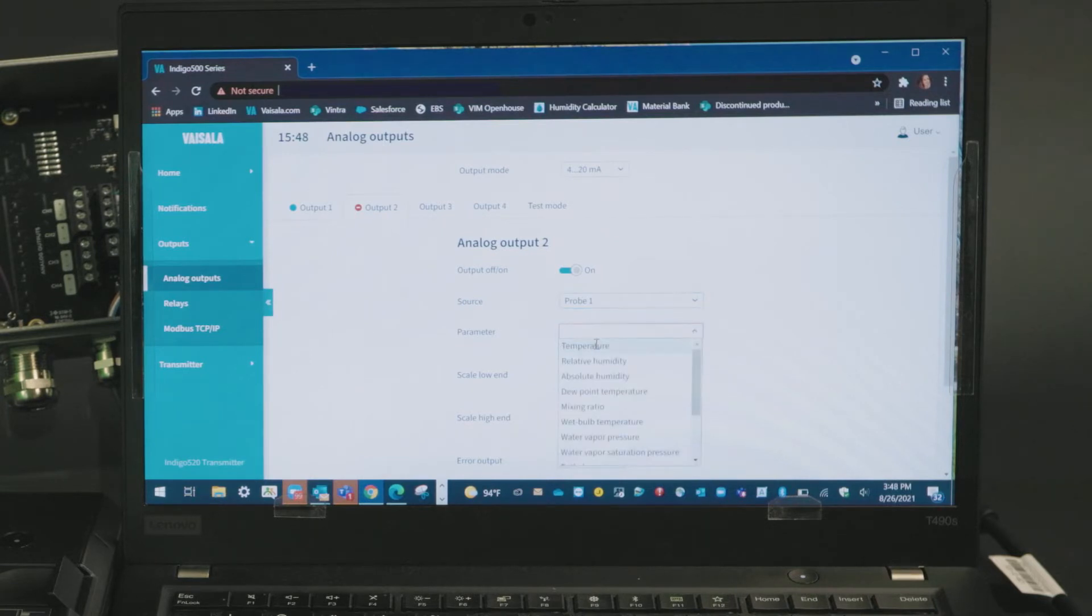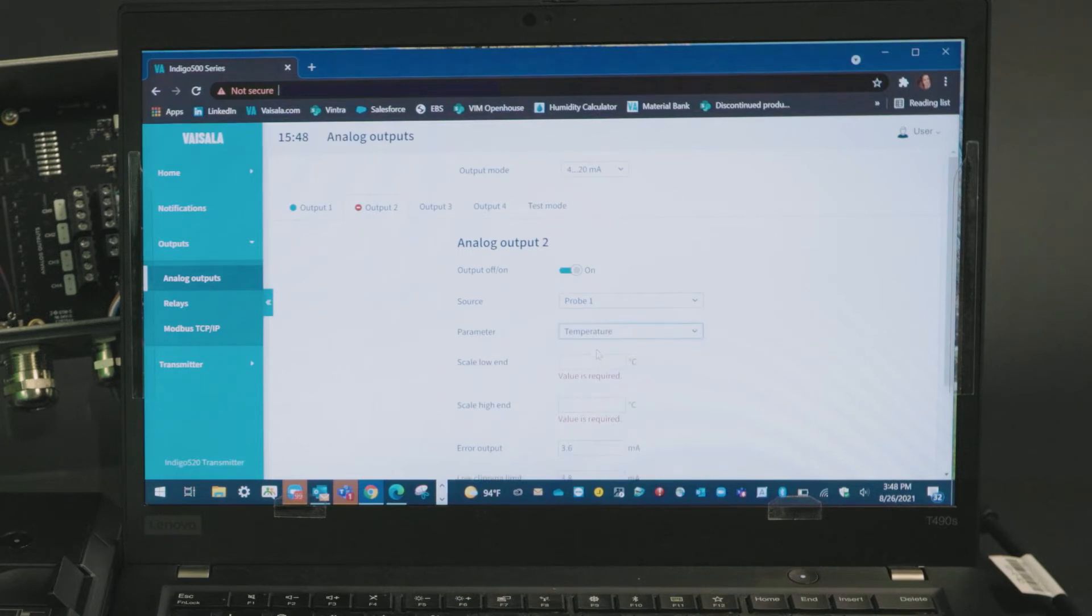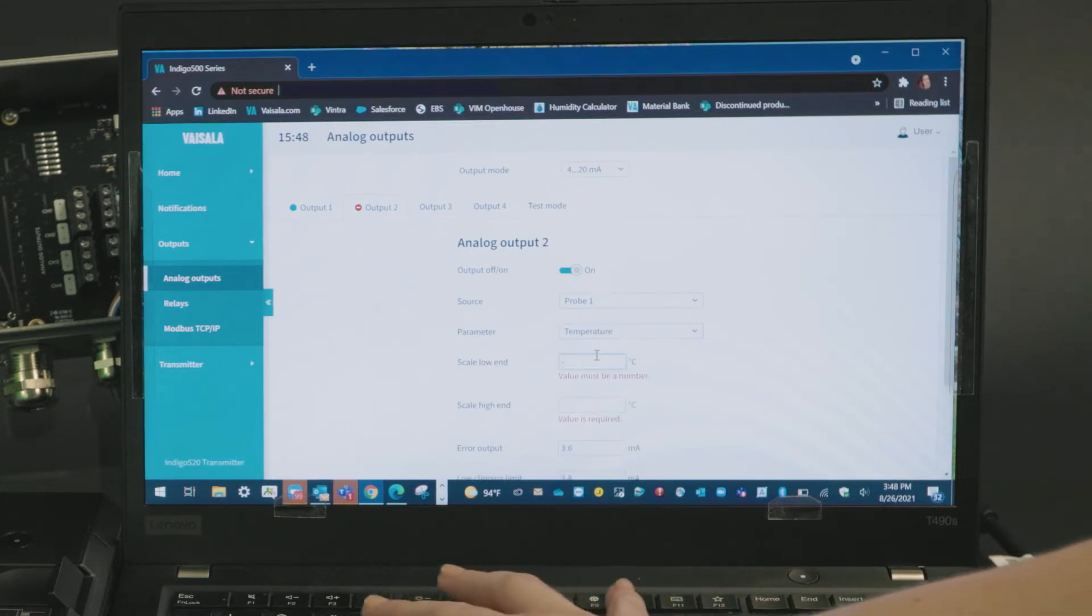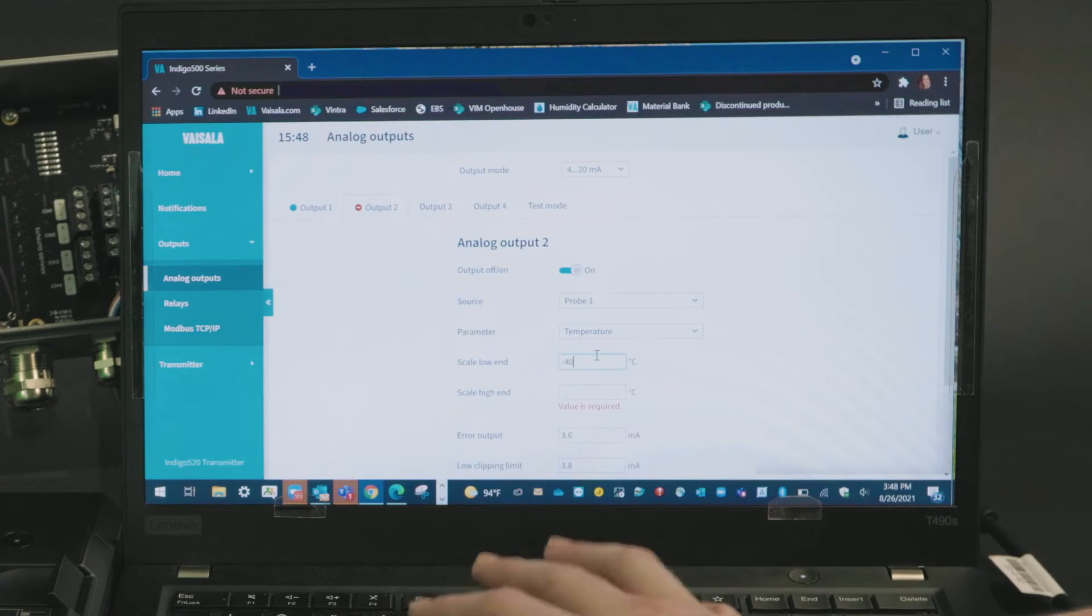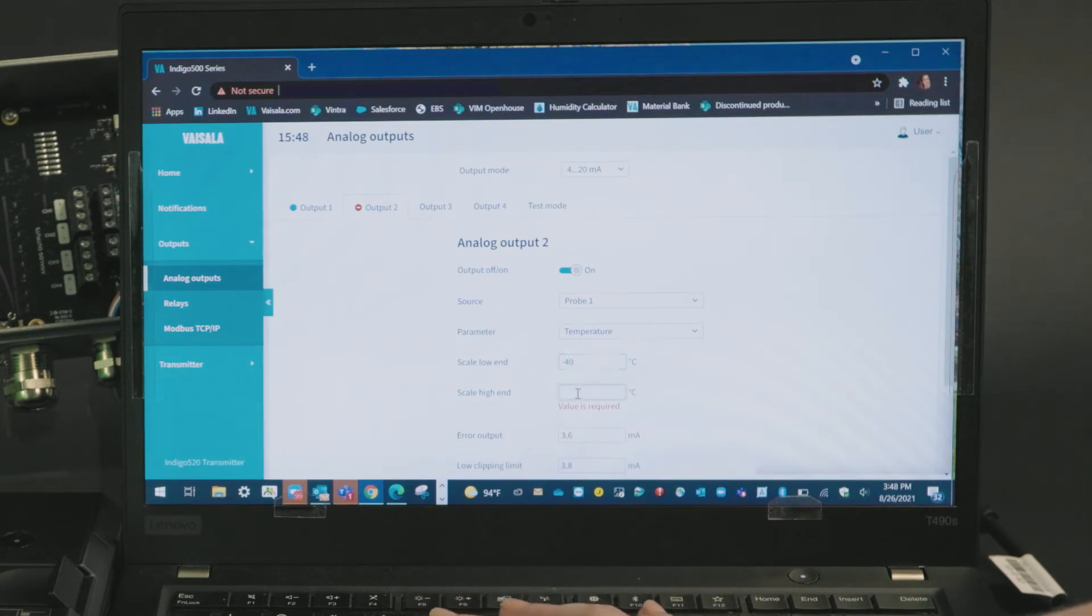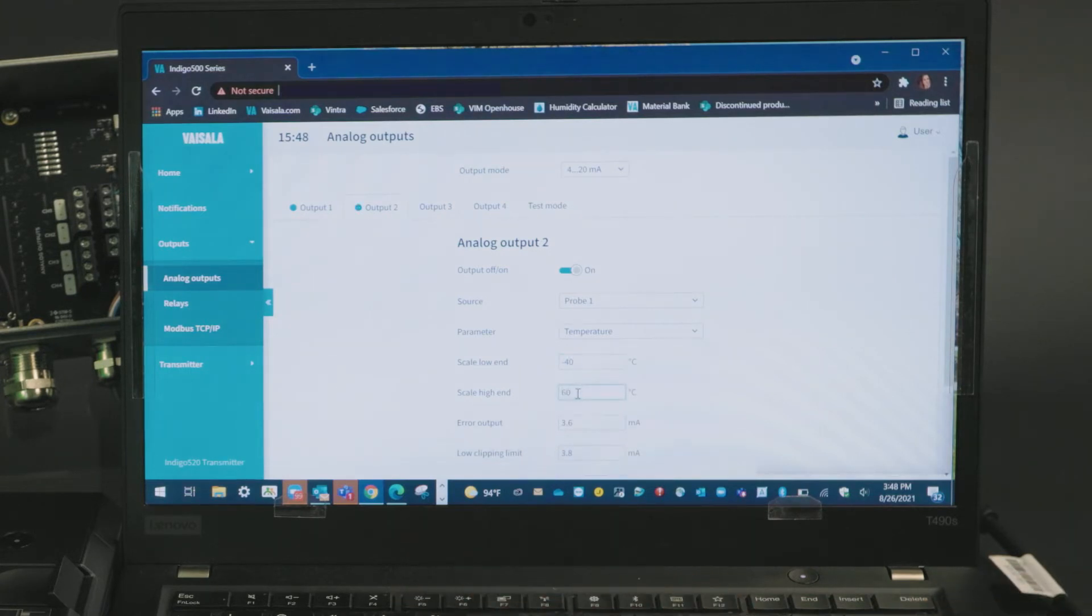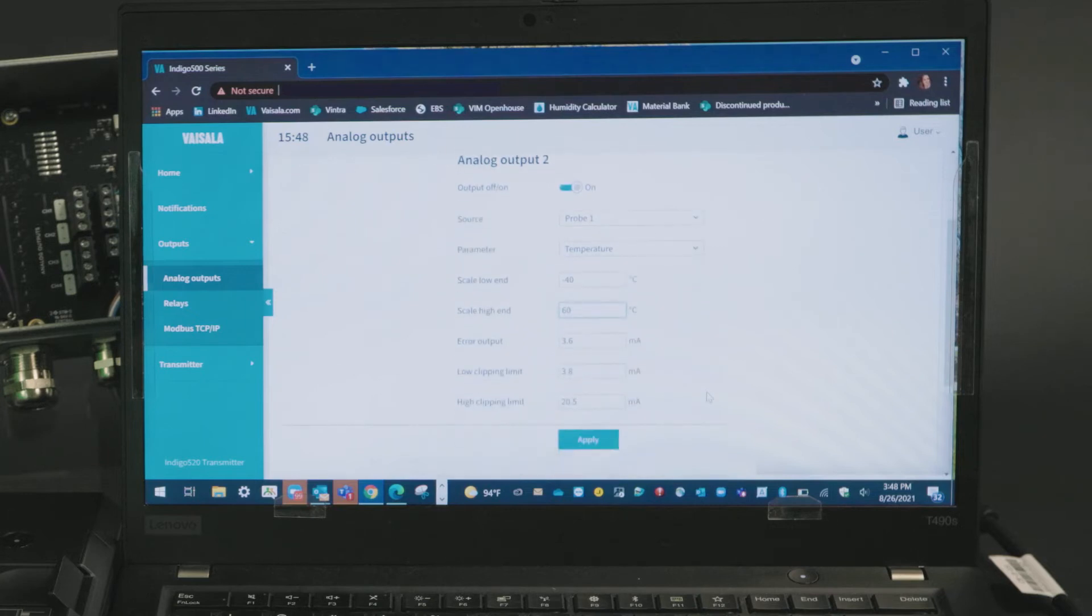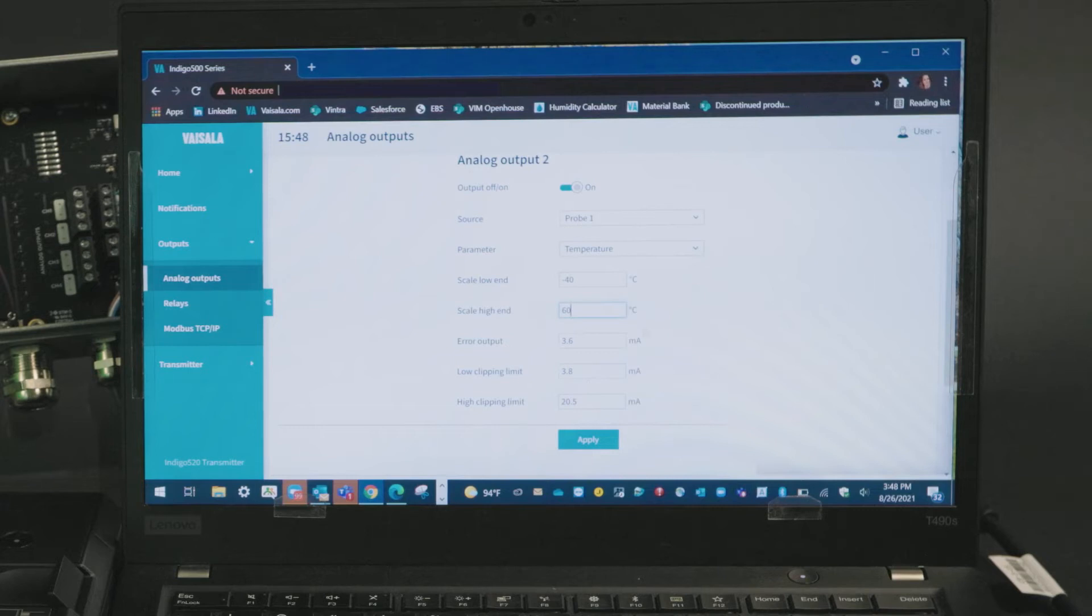I'll select the parameter temperature and I want to scale this to match a previous unit which used scaling from minus 40 degrees C to 60 degrees C. You can also configure the error output and clipping limits here though defaults will be shown. I'll go ahead and click apply.